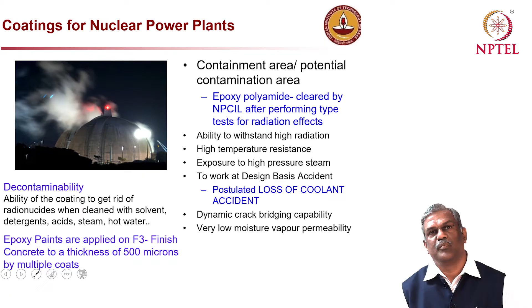The epoxy which is used here is not the normal epoxy. It is subjected to a variety of tests by the government, NPCIL, and then they accept a particular coating, whether it is able to take care of radiation resistance, the ability to withstand the radiation. That is the most important requirement. Secondly, can it bridge cracks? That is also a very, very important requirement. Nuclear plants have a typical painting system, and we will not be detailing too much into that. We only require a good concrete, moisture-free, F3 finish, and then you start applying epoxy in multiple coats.